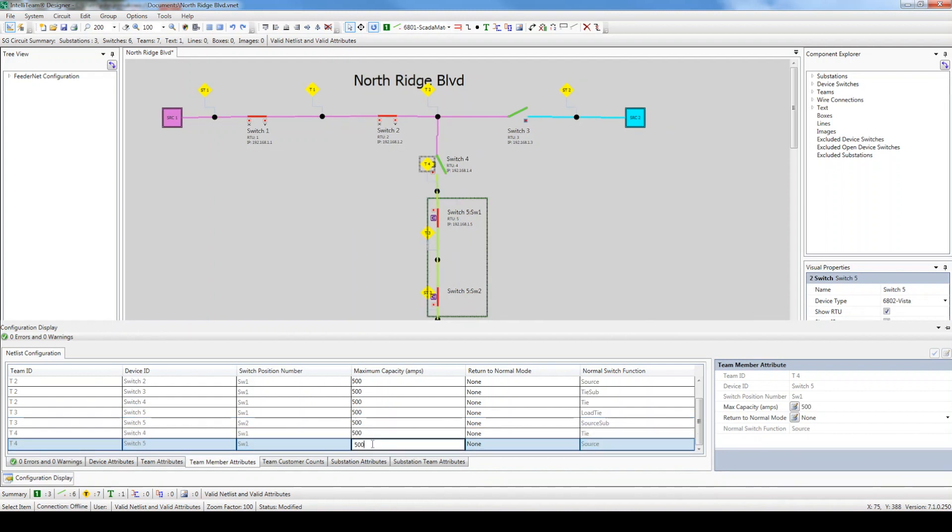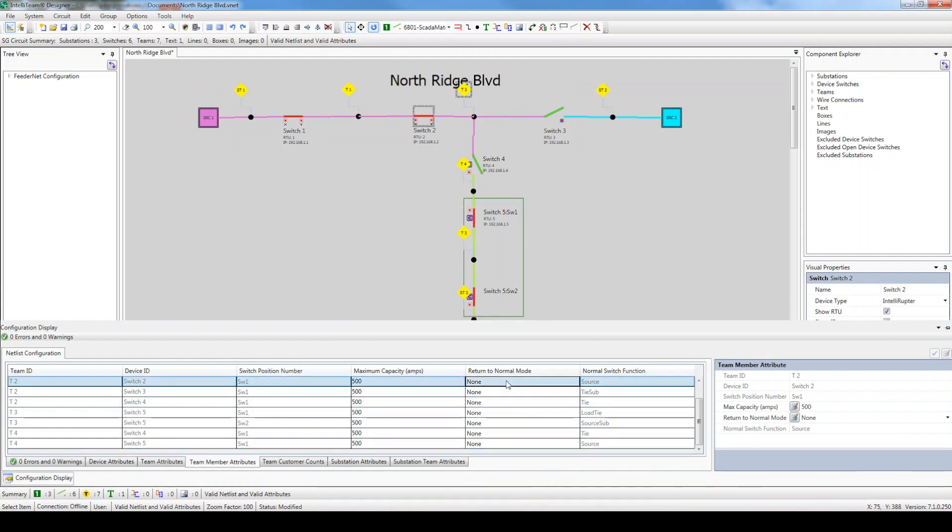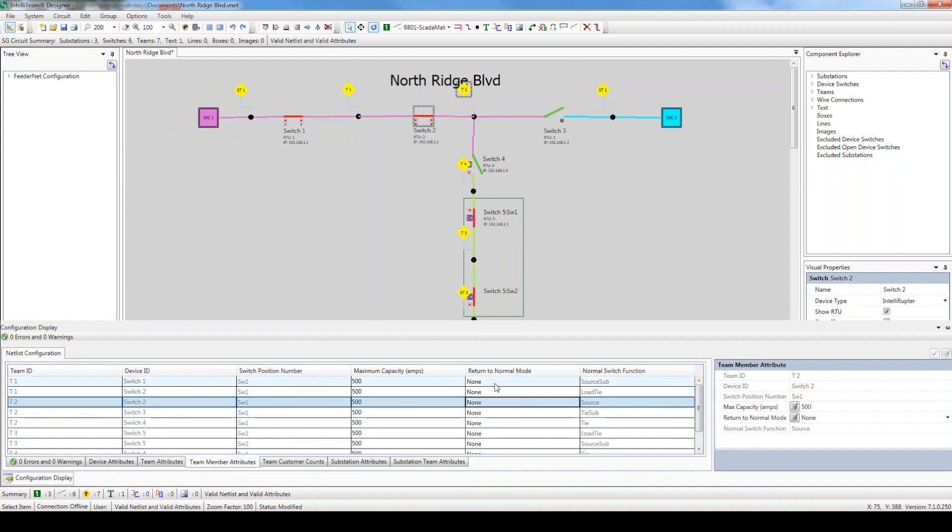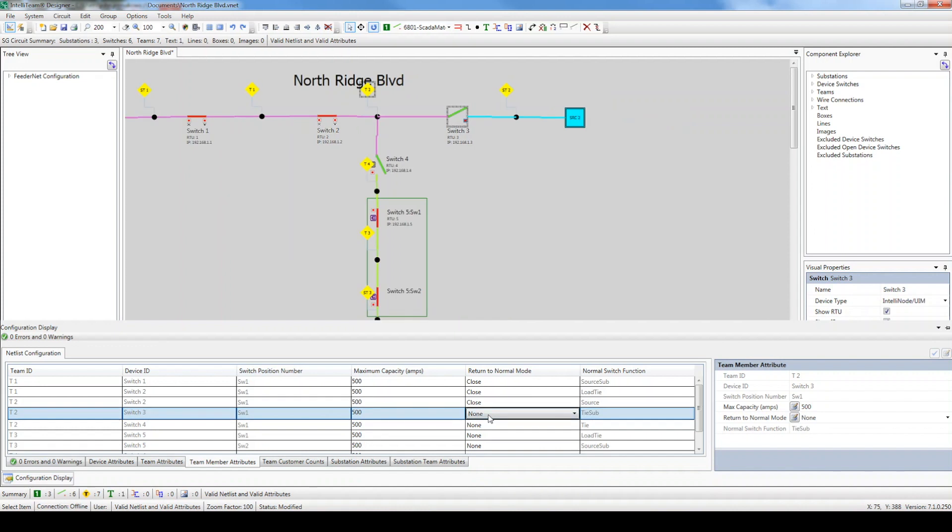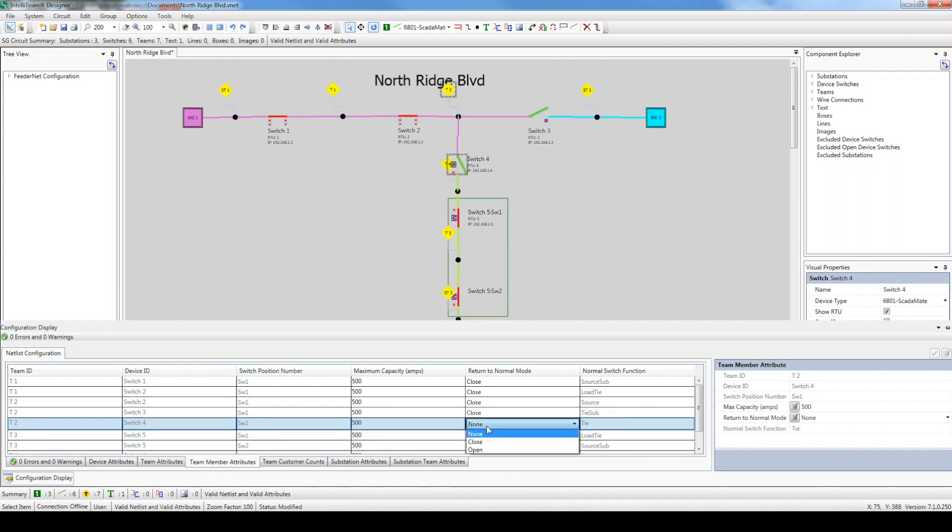The Return to Normal Mode setting serves two purposes. It allows the user to configure a manual return to normal or an automatic return to normal. If automatic, the user must select between an open or closed transition return. Let's set this to closed for each team member.